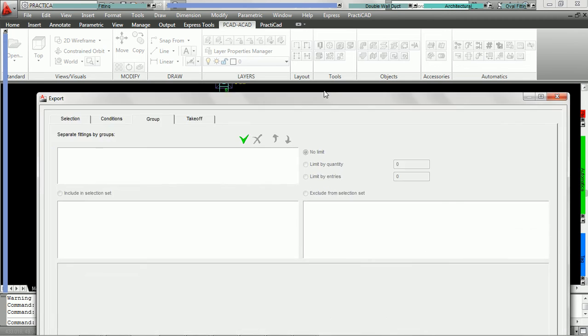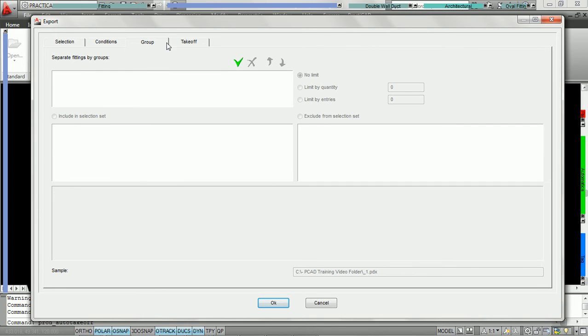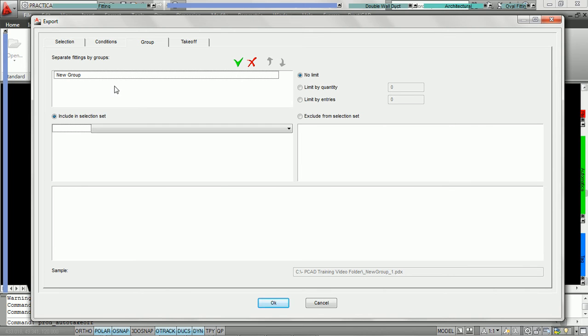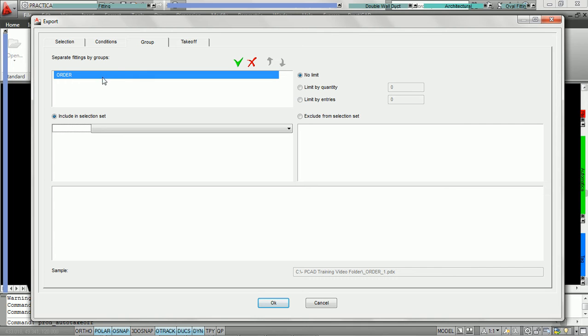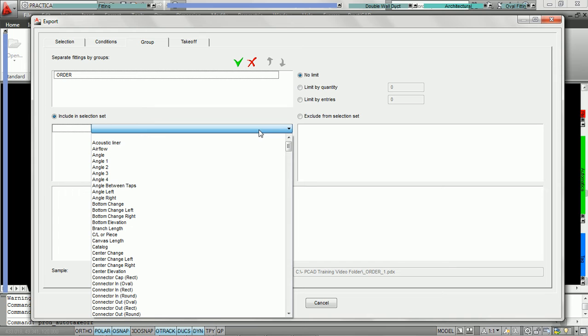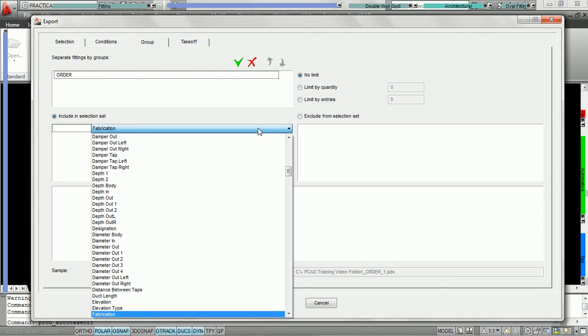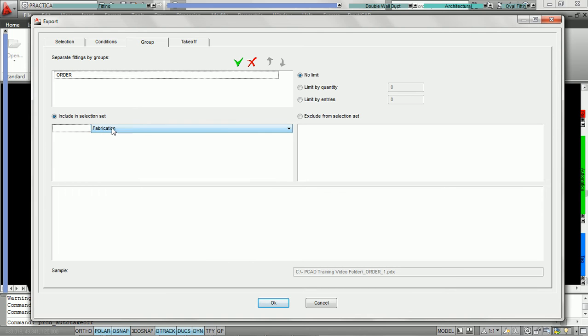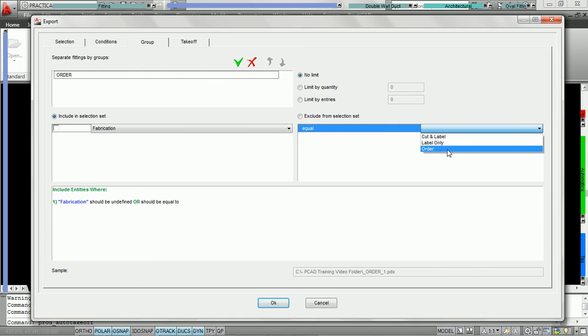We're going to bring our export window back up. We're underneath the group tab and we're going to create a group by clicking on the add icon — the green check. PractiCAD is going to ask us to name the group. We're going to call this group 'order' and hit enter. PractiCAD will now ask us what conditions the fittings have to meet in order to be part of the group order. We're going to open up our condition set, navigate to fabrication level by hitting F, and set fabrication equals order.